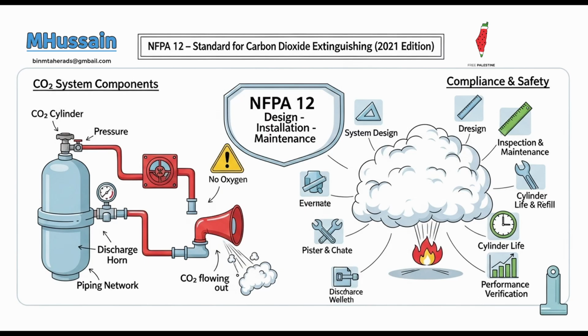This is an absolutely vital safety feature, specifically designed to prevent the flow of carbon dioxide to protected areas during maintenance, testing, or any time personnel are intentionally present. So you lock it closed when people are inside. Precisely. It's also mandated in any location where discharged CO2 could migrate and create a hazard in an adjacent area. Prevent leakage into other rooms. Right. The practical implications are significant.